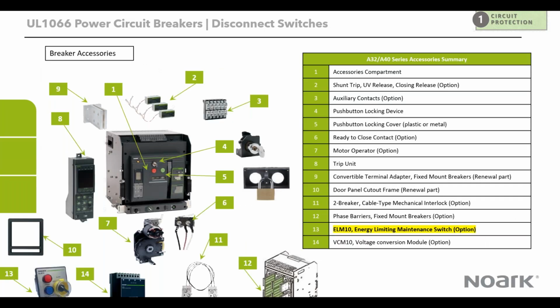They have a number of accessories here, which I will not go into in a lot of detail, but I would like to talk about the energy limiting maintenance switch. I mentioned earlier on that sometimes you can have the occurrence of arcs, whether through normal operation or as a result of a fault. When you have those arcs, the NEC requirement is that you must have a way of quickly telling the breaker to not wait for any preset delay and to react quickly to the fault. When it does that, it reduces the amount of electrical energy that can flow in your system. We do that using the ELM10, the energy limiting maintenance switch, which is the device number 13 here. That's an important device, and we have it for the 1200 amps enclosed breaker and also the power circuit breaker.